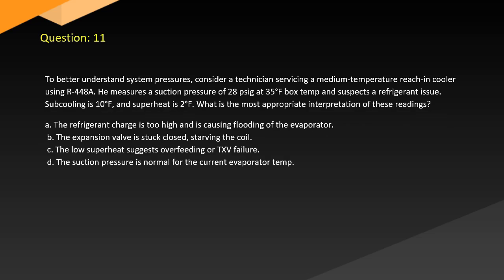Question 11. To better understand system pressures, consider a technician servicing a medium temperature reach-in cooler using R448A. He measures a suction pressure of 28 psig at 35 degree box temp and suspects a refrigerant issue. Subcooling is 10 degrees and superheat is 2 degrees. What is the most appropriate interpretation of these readings? A. The refrigerant charge is too high and is causing flooding of the evaporator. B. The expansion valve is stuck closed, starving the coil. C. The low superheat suggests overfeeding or TXV failure. D. The suction pressure is normal for the current evaporator temp.